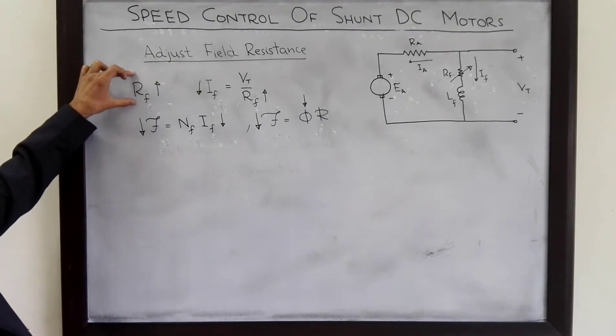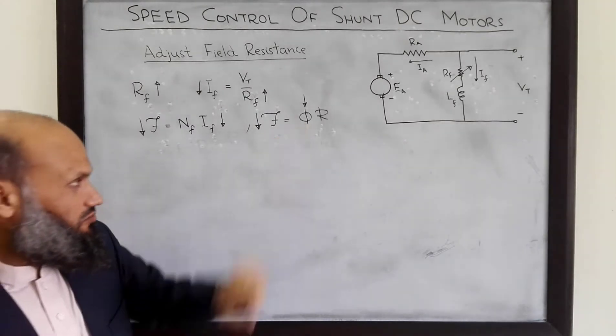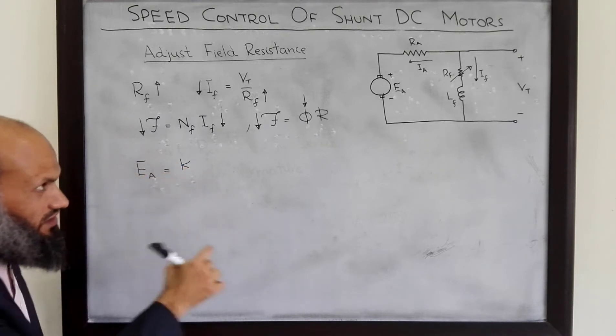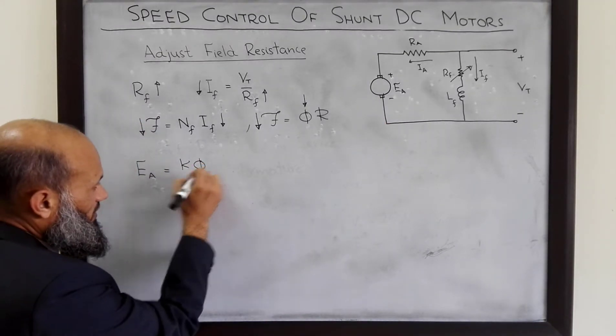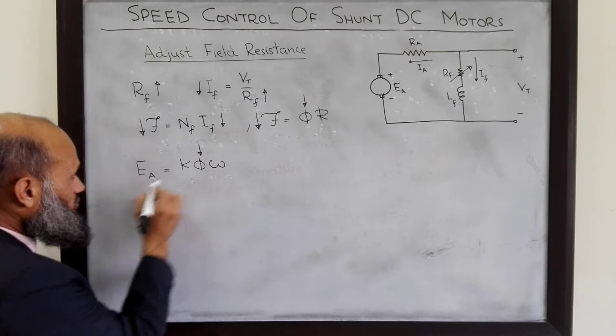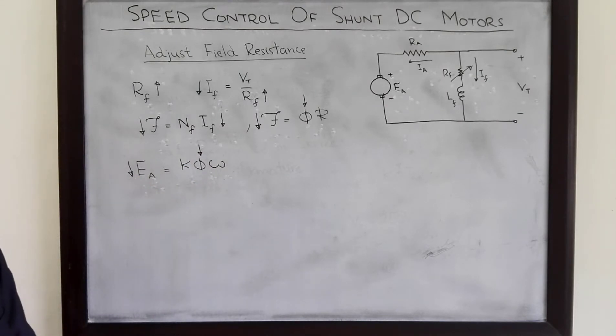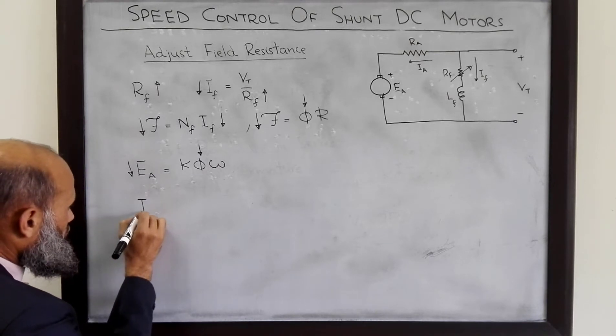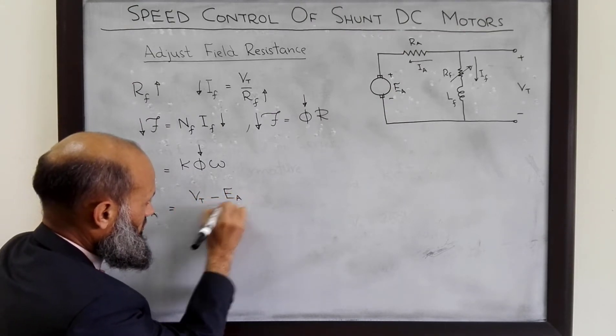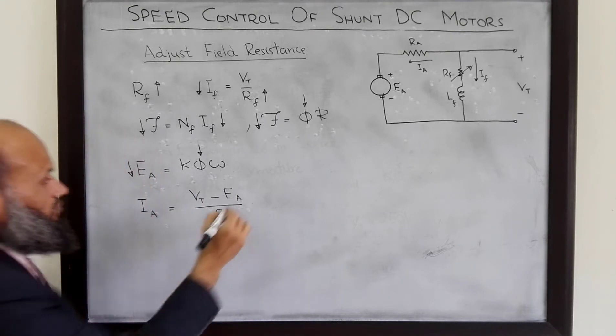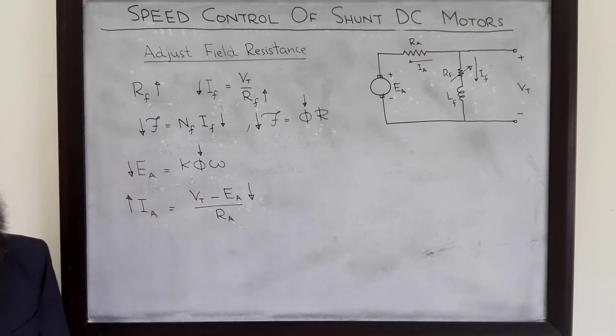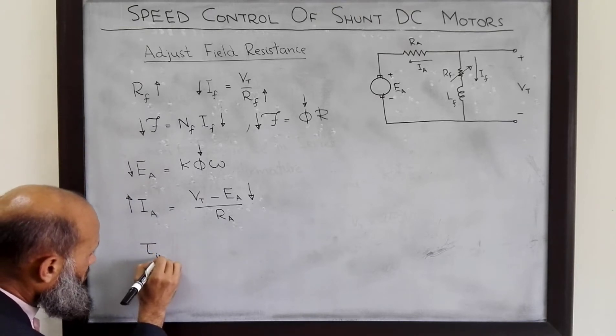One effect of an increase in RF is a decrease in flux in the machine. Furthermore, EA, the generated back EMF, is given by a constant multiplied by flux multiplied by the rotational speed of the rotor. So if flux is reduced, the generated voltage EA will also reduce. The armature current IA is given by the terminal voltage minus back EMF divided by the armature resistance, so if EA decreases, this difference increases and IA will increase.